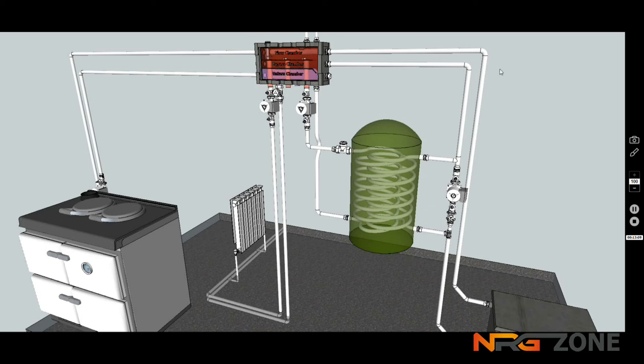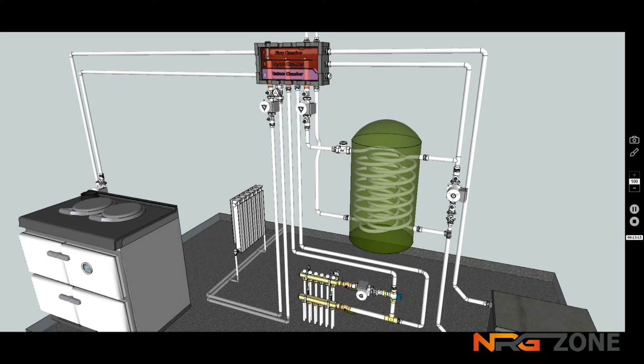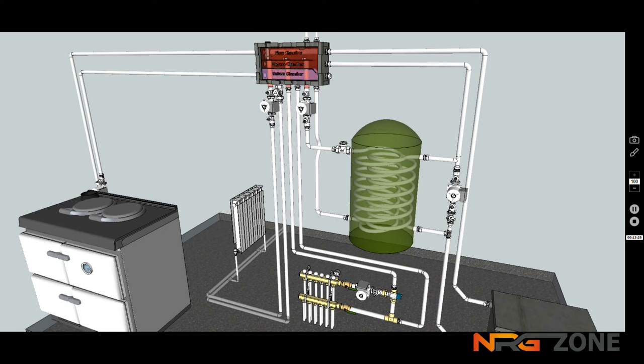If we now want to move on to, say, an underfloor heating circuit, we could simply put in the circuit in this fashion, where we again take our hottest water down and into a temperature mixing valve. The mixing valve would allow for whatever temperature is necessary to be circulated. If the underfloor pump is working, it will be pushing, let's say, 35 degree water around the floor, and heating the floor to whatever the manufacturer's design would say it should be.